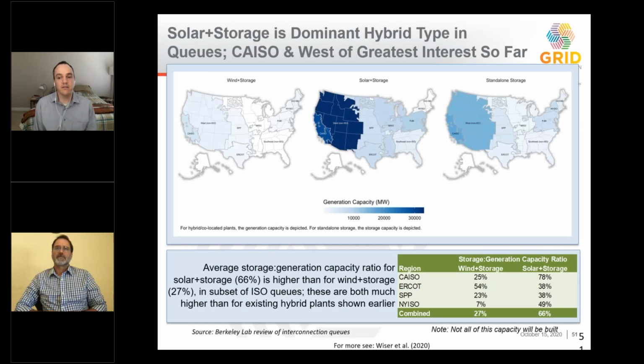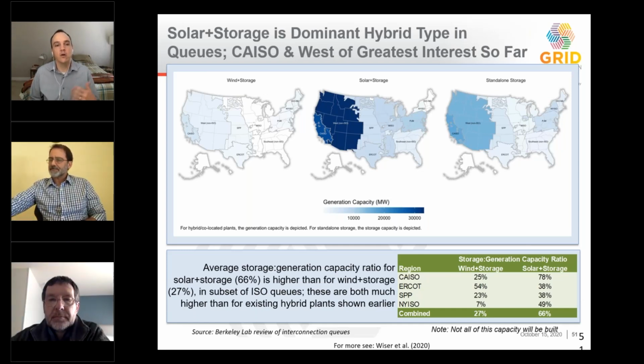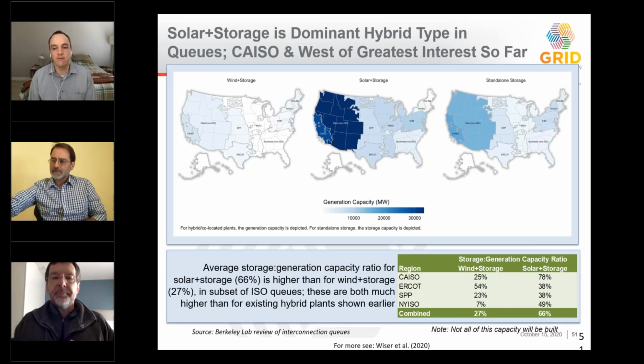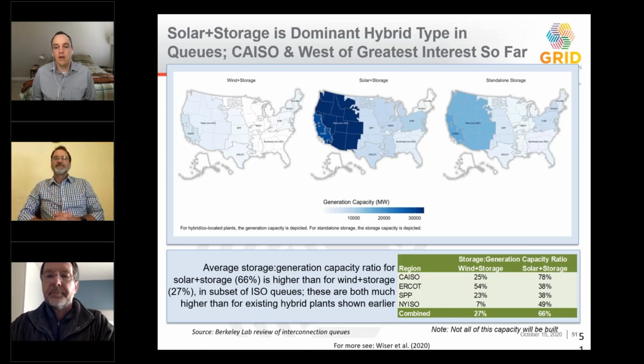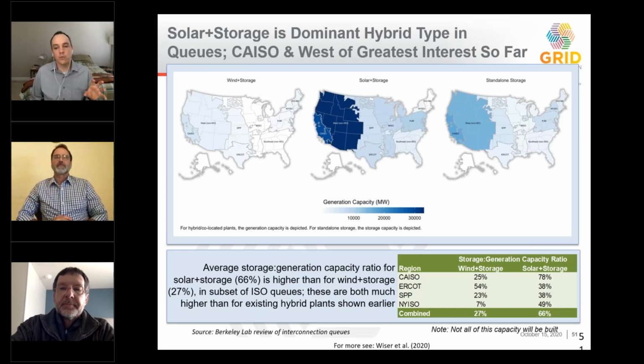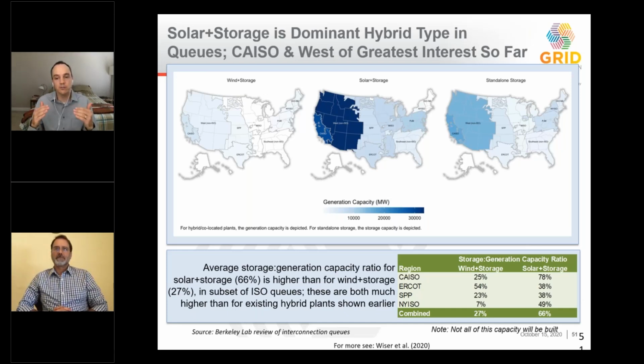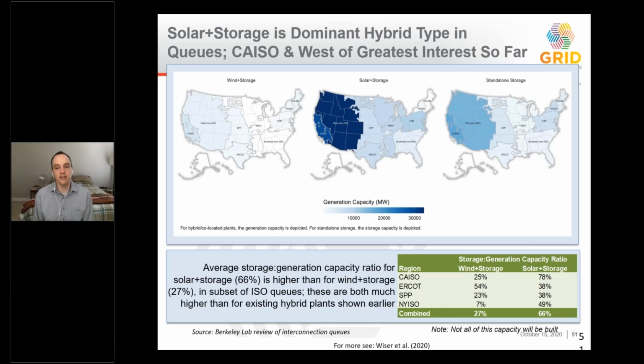The bulk of this hybrid activity is happening with solar and storage, and most of that is happening in the Western United States, where we see increasing levels of solar penetration. For solar, the batteries tend to be sized about 66% of the nameplate capacity of the solar plant, so they're fairly large relative to the plant. Whereas for wind plants, those batteries are sized smaller, at only about 27% of the wind nameplate capacity.